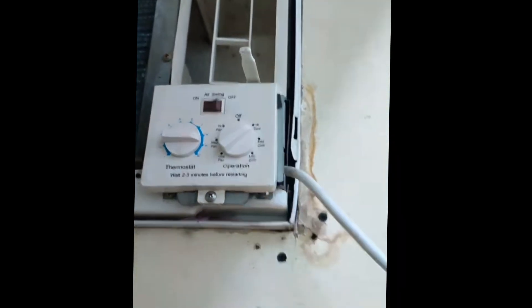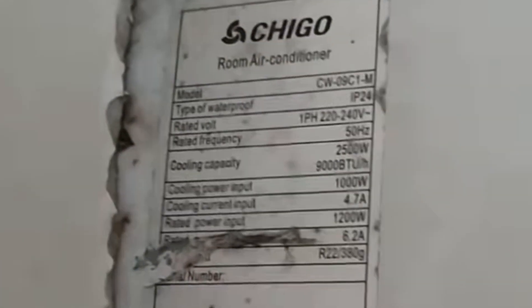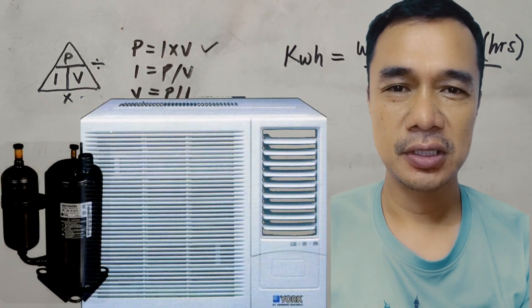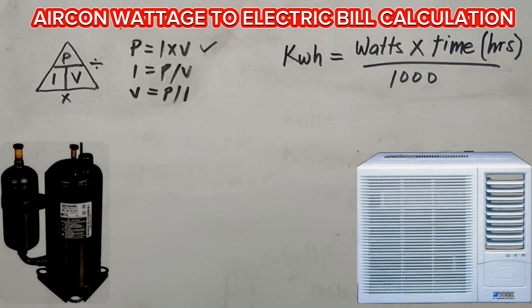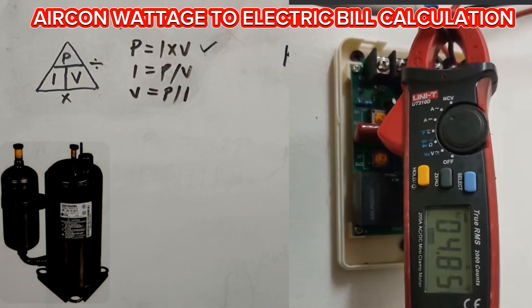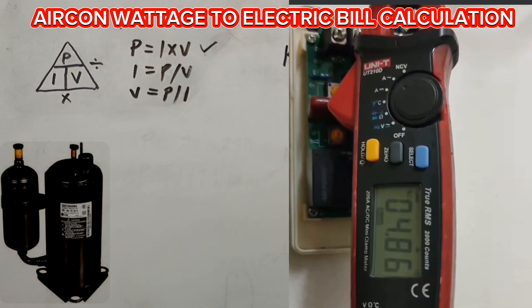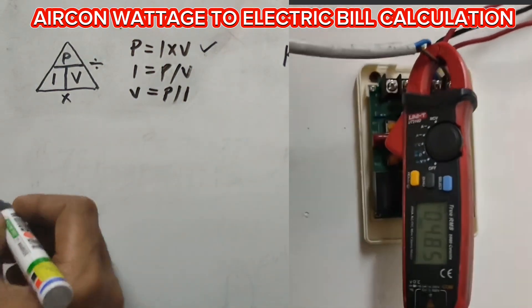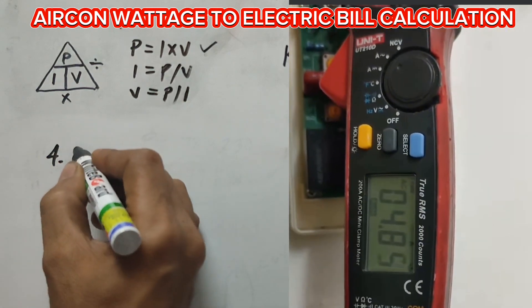Three-fourth turn for the thermostat, and the selector is set to high — we got 4.80 ampere here, and in the label this is 4.7 ampere. Welcome to my YouTube channel! Today we're going to compute the power consumption of a one-horsepower window-type air conditioning unit. This aircon is non-inverter, or conventional. The running ampere for a one horsepower unit in my place is rated 4.8 ampere.